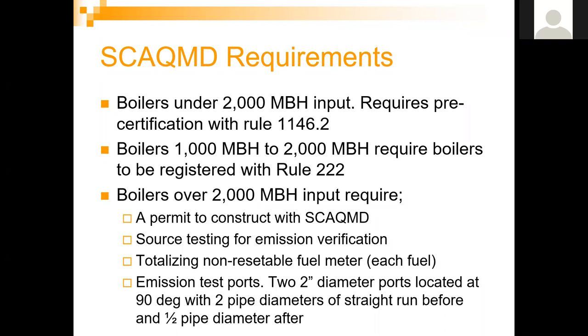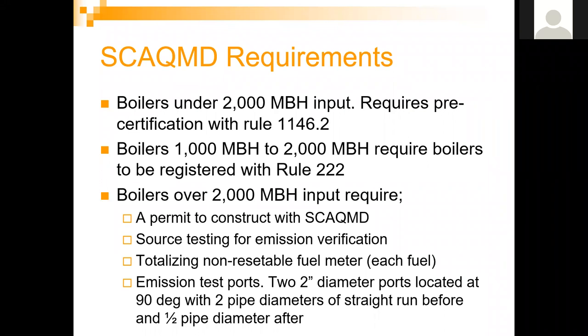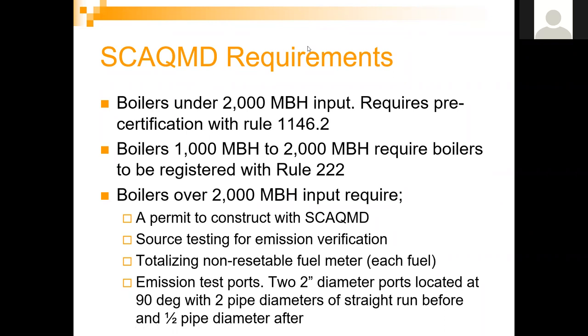Boilers over 2,000 MBH input require a permit to construct with South Coast AQMD. You want to pull those permits as early as possible in the construction process to get locked in on what emissions will be required, because the AQMD can and does change its regulations. You want to pull permits early and lock in what South Coast AQMD will require from an emissions perspective. They also require source testing for emission verification after the boilers are installed and running.